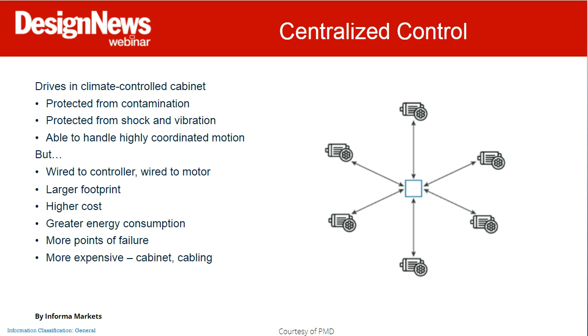But for other applications, we can look at distributed control with smart drives that have the ability to act as controllers, because they can be put together in daisy chain controller architectures—master-slave, where one drive is master to many slaves, or each one is a master of the next. You're hanging your drives out on the motor, so you have much less cabling. You can apply things like regenerative braking with some of these smart drives. You've got the PLC handling most of your machine logic, but the drive is actually able to take care of much of the motion, and again we get our savings with cabling.